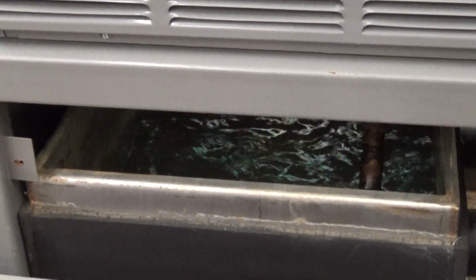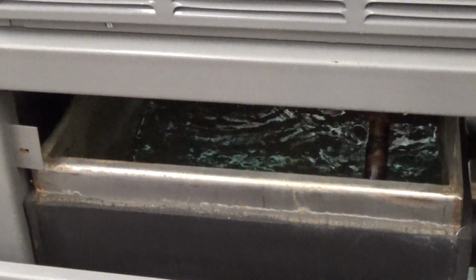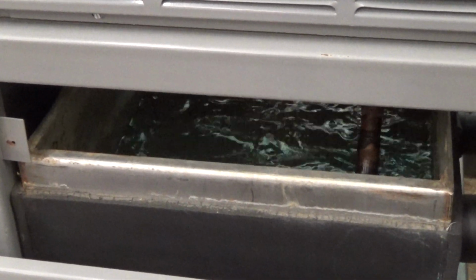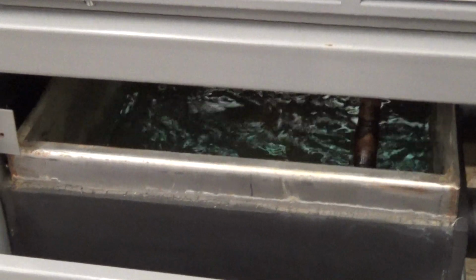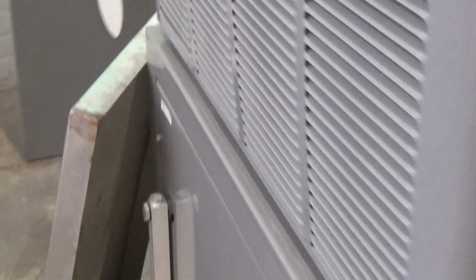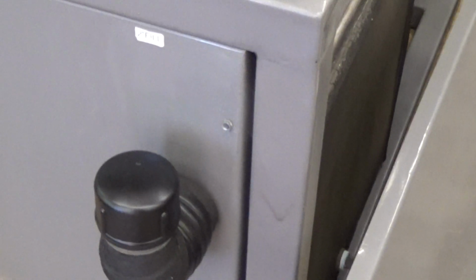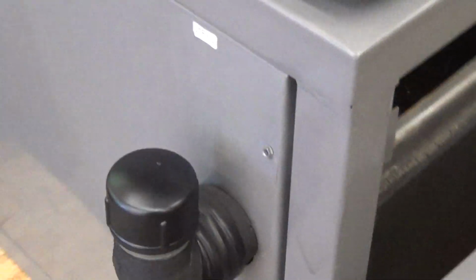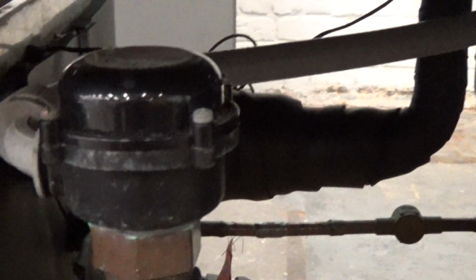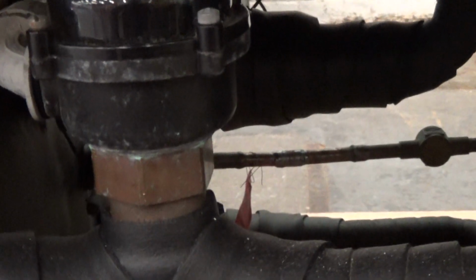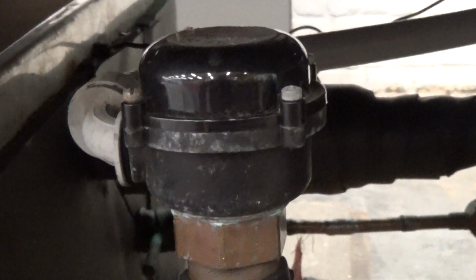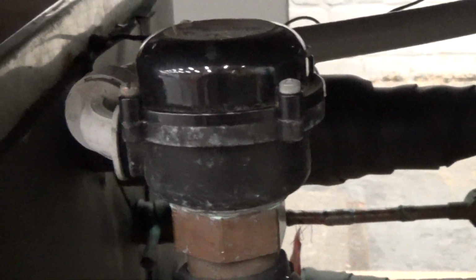We have the tank about half full right now. You should always run it full. If this is going outdoors where it is in the colder climate, you should be running 45% glycol solution. Like I said, we do have the lid there. Here's the fill port if you want to fill the glycol solution in from there. The unit does have a flow switch, and in all these we take them apart, lubricate and make sure the flow switch is working okay. If we don't see flow, the unit will shut down.